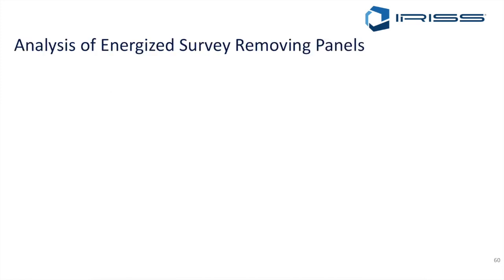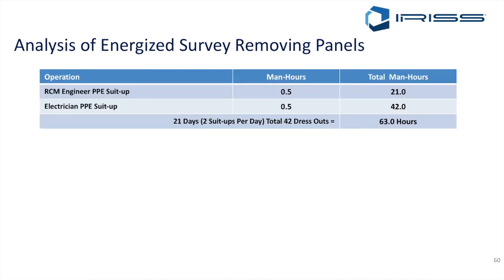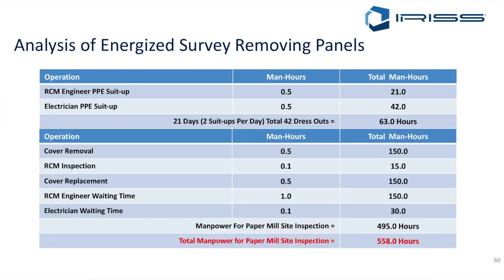We analysed the energized survey required with removing panels. Obviously, PPE suit up time, we were looking at approximately 21 days, 2 suit ups per day, 3 guys suiting up: 21 hours of PPE suit up time for the RCM engineer, and 42 hours of suit up for the 2 electricians, which is 63 hours. Now, this was meant to be 2 suit ups, but in fact there were a lot more, because it was August in a paper mill in South Carolina, which is extraordinarily hot. We were looking at probably 4 to 6 suit ups a day - you just can't sit in PPE, it's far too warm.